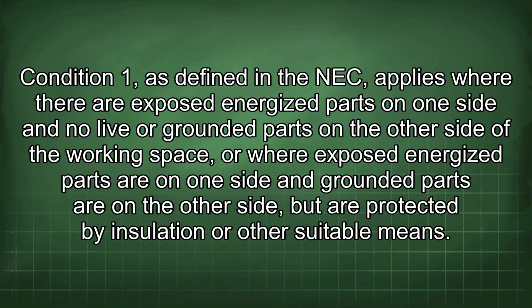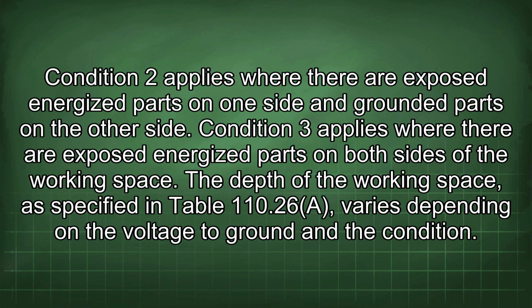Condition 1, as defined in the NEC, applies where there are exposed energized parts on one side and no live or grounded parts on the other side of the working space, or where exposed energized parts are on one side and grounded parts are on the other side, but are protected by insulation or other suitable means. Condition 2 applies where there are exposed energized parts on one side and grounded parts on the other side. Condition 3 applies where there are exposed energized parts on both sides of the working space.